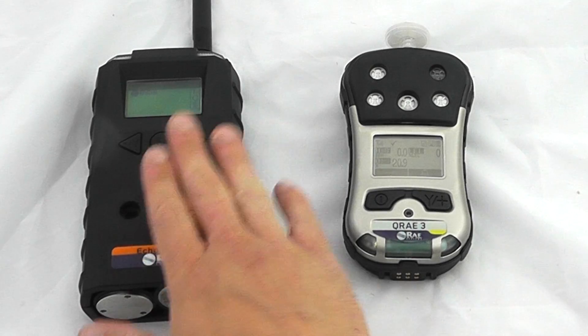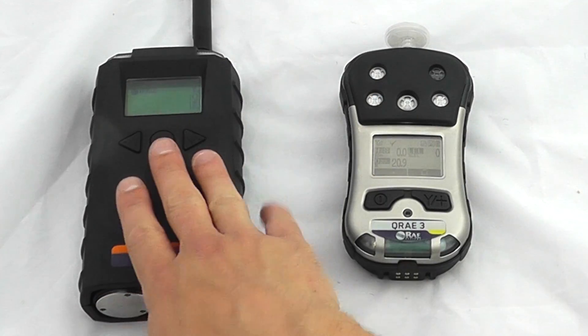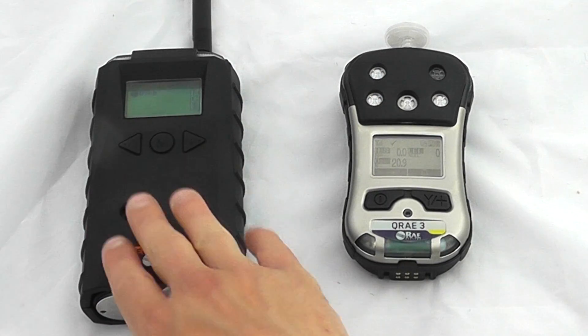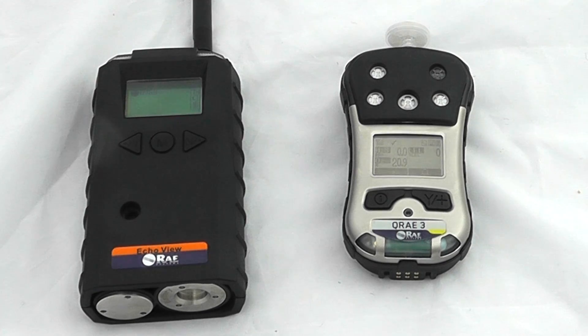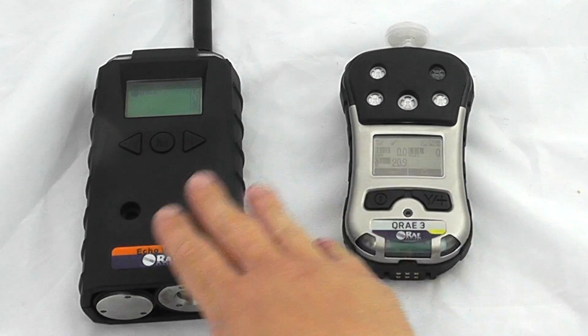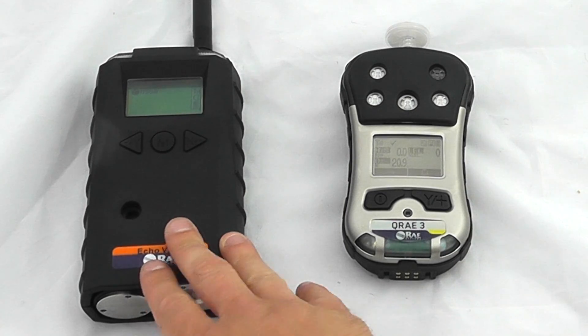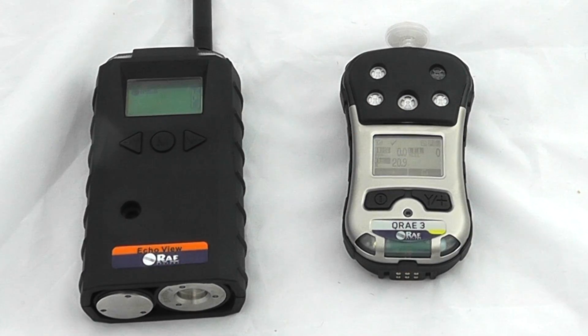Any alarms on this device will now show up on the Echo View remotely. The distance limit depends on the site conditions. These are high-quality radio frequencies, but if you're in a stainless steel box, the signal might struggle to get through. Be aware of line-of-sight issues. If I apply some gas to the QRAE 3, we'll see an alarm reflected on the Echo View network.